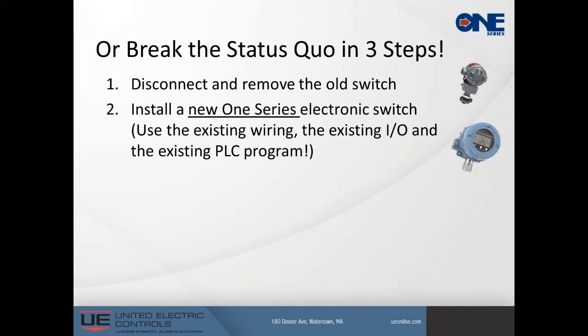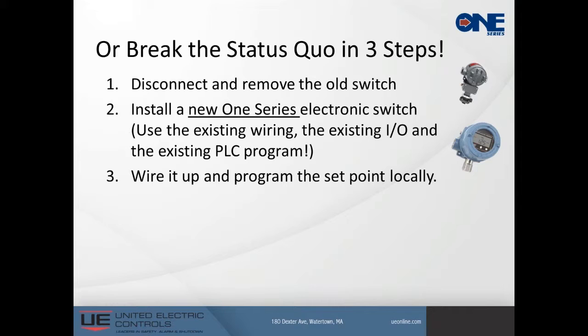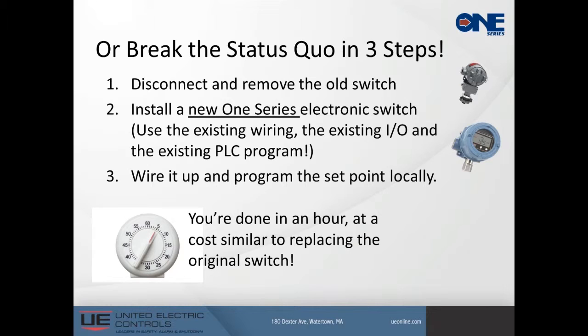So again, disconnect the switch, install the new One Series electronic switch, and in this case we're going to use the existing wiring, the existing I/O and the existing PLC program, the ladder logic. It's all the same infrastructure. Nothing has to be changed other than we're going to a new device that has no moving parts in it. Wire it up, program the set point locally, and you're done. And this is a major cost savings that we can promote throughout the industry to bring value to the technology that we have available in the new One Series.